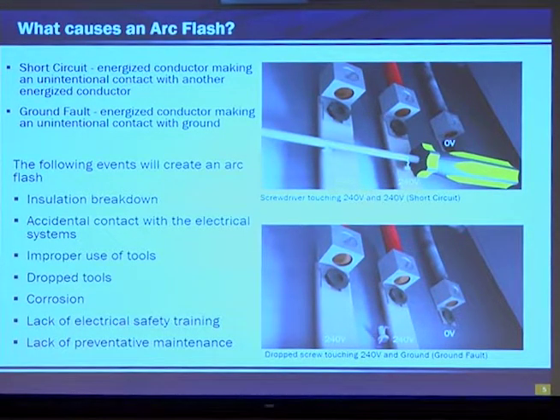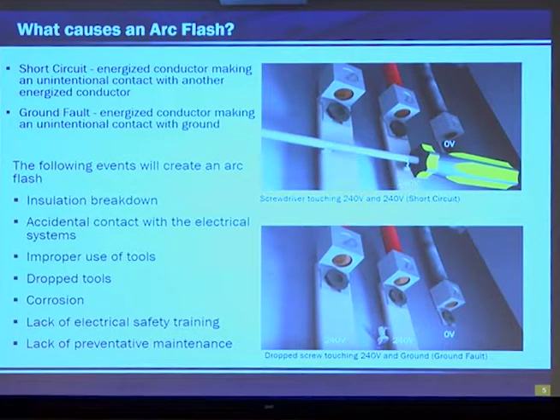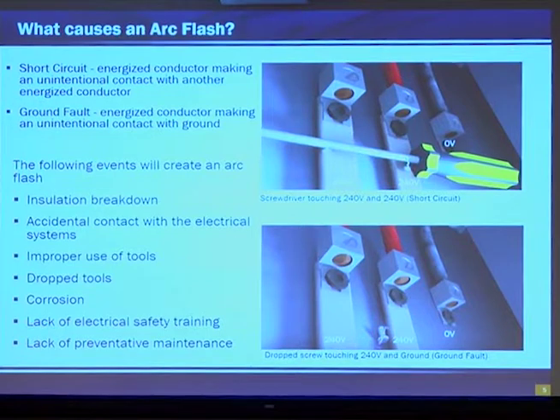So there are two things that will cause an arc flash, a short circuit and a ground fault. Let's define these terms. A short circuit is when an energized conductor makes an unintentional contact with another energized conductor, as opposed to a ground fault where an energized conductor makes an unintentional contact with ground. The first picture shows an example of a short circuit creating an arc flash. A screwdriver is accidentally dropped between two phases, creating an arc. The second picture shows an example of a ground fault creating an arc flash. A screw is dropped in the electrical service, making contact between a phase and ground, creating that arc. Now, these are just two scenarios. There are several other events that will cause an arc flash, such as insulation breakdown, improper use of tools, corrosion, lack of preventative maintenance, and so on.